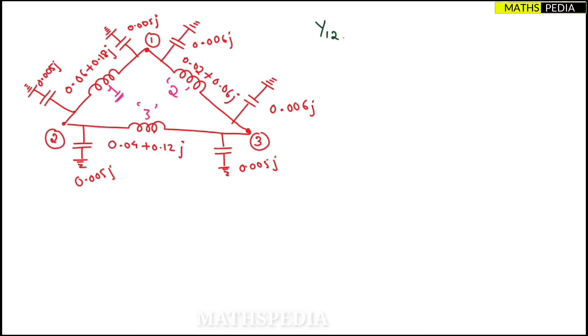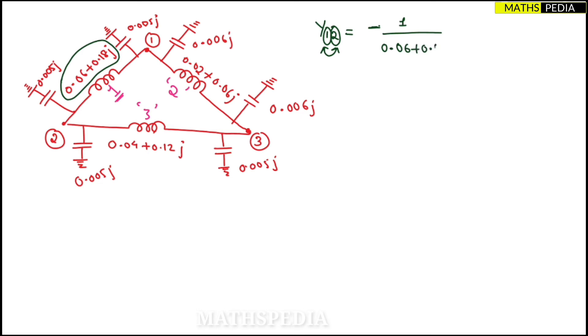Now for Y12, a non-diagonal element: look at what is between node one and node two. There is one impedance. For non-diagonal elements, always take the negative of the admittance — that is, minus one divided by the impedance between those nodes.